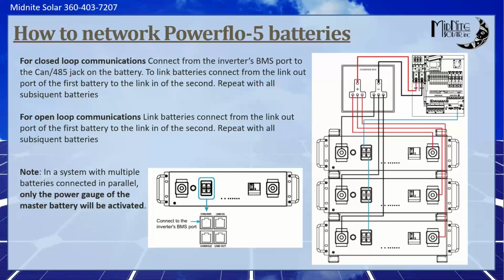Battery positive and negative connections, daisy chain using large enough conductors versus a combiner box. I kind of just touched on that, but that's really what it boils down to. If you've got 8 batteries in a single stack and you run, say, 4-aught cable between every battery, pulling the inverter negative off the top battery and inverter positive off the bottom battery, that will work, but the middle batteries will lag behind a little in both directions. Whereas if you run all 8 batteries using number 4 wire to a lithium battery combiner, then run your cables, they all get the same amount of current. So daisy chaining batteries works on a small scale, but as the system gets larger, I try not to do that.